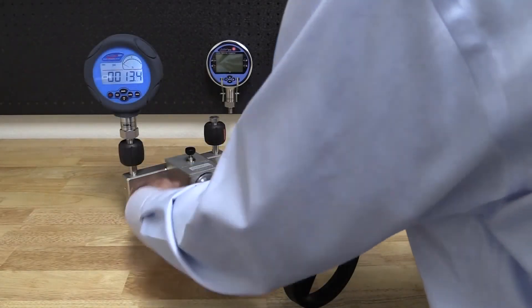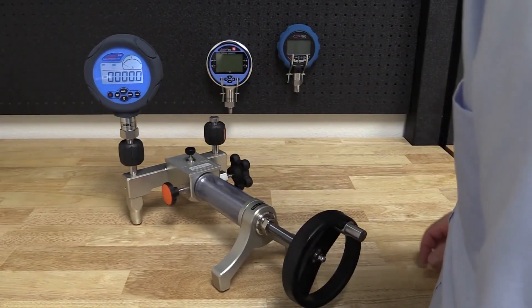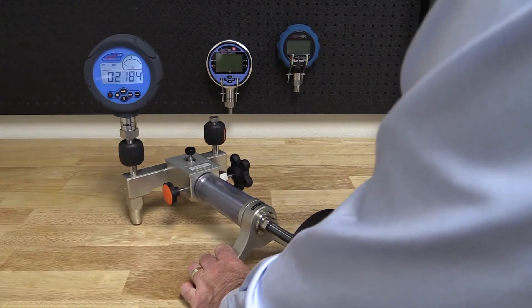Once you see a good vacuum being pulled and very few bubbles emerging in the liquid reservoir, then we are ready to start generating pressure. You should easily be able to generate full-scale pressures with less than half the stroke of the main screw press.